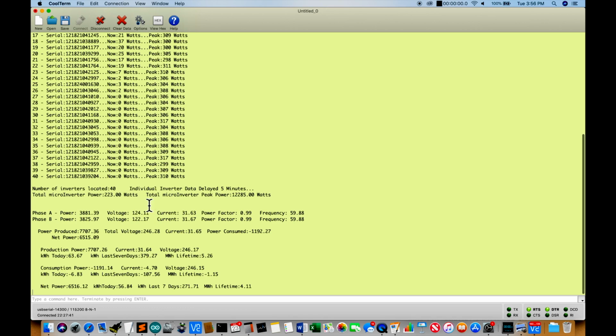And that's really the end of the inverter inventory data. This is some meter stream data that gives us a pretty real-time level of power on phase A and phase B. That's not really accurate -- Enphase actually calls it that, but phase A and phase B, there's only 2 wires, and they're measuring each of them compared to ground for voltage and current and power, but listing the power factor and frequency for each separately.